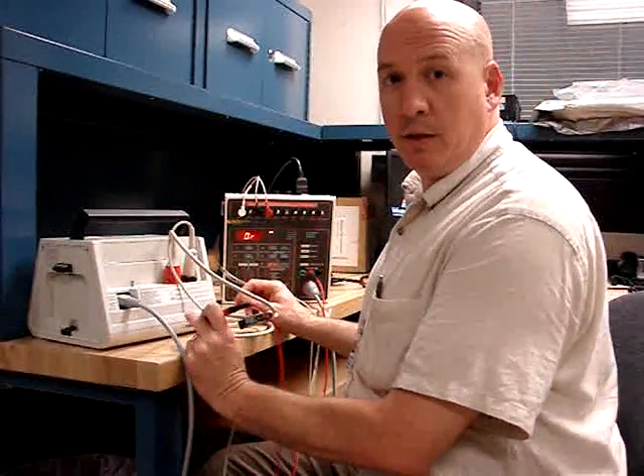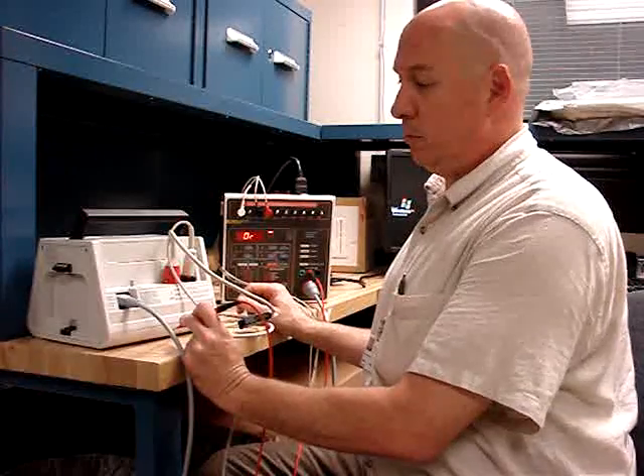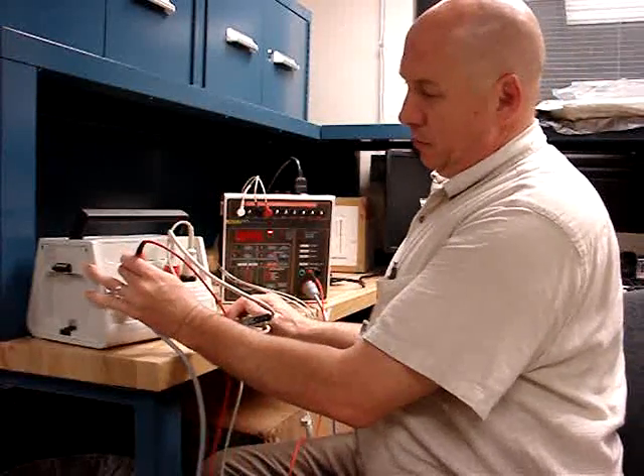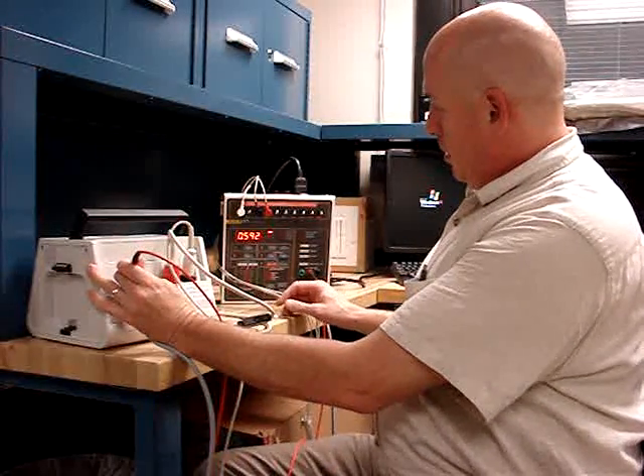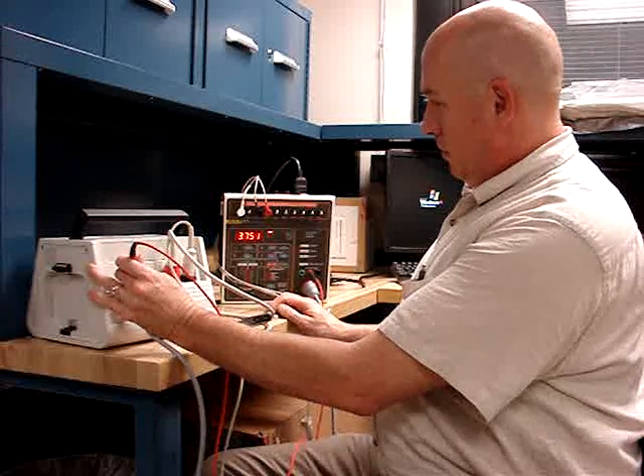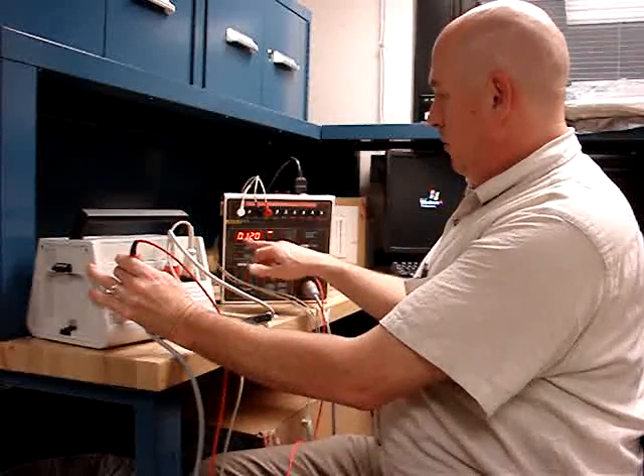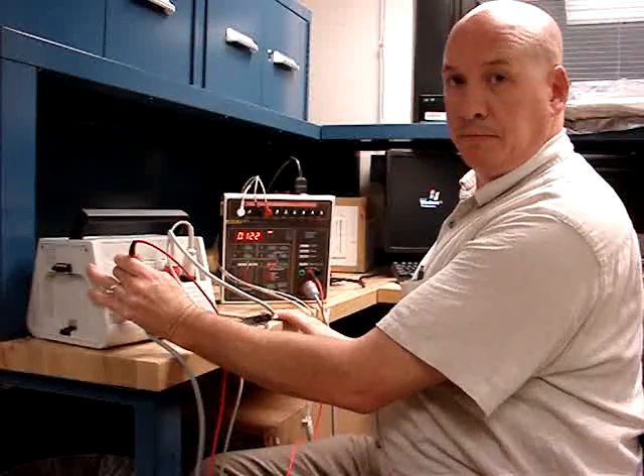My name is Jeff Howard, and for my portion of the PM procedures for the Zoll M-Series defibrillator, I will be doing the ground leakage check, the chassis leakage check, lead leakage check, and the pace analyzer checks. Grounding resistance check should be less than 0.5 ohms. What we're checking here is from the ground point to here with a good connection. So we have 0.12 ohms.